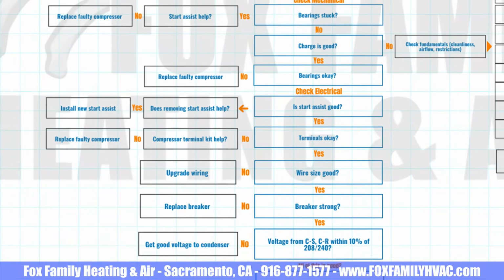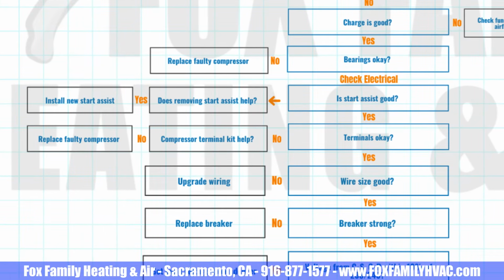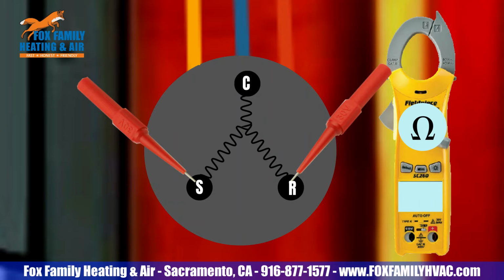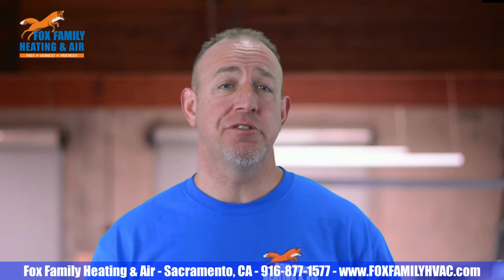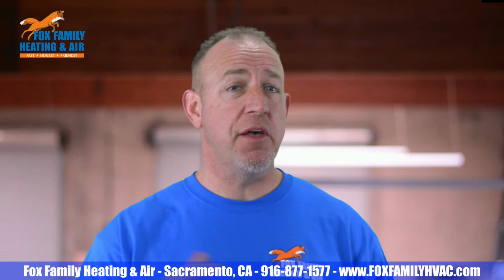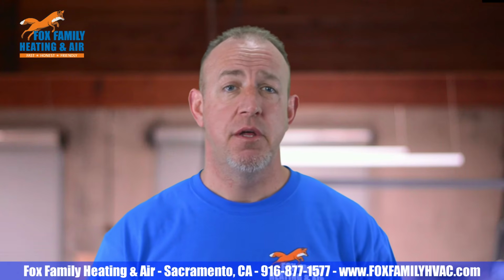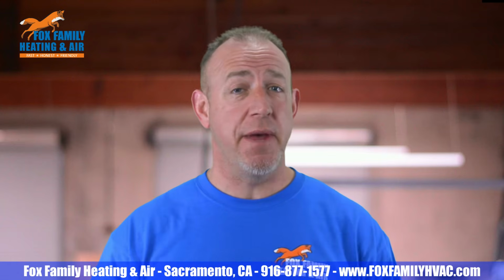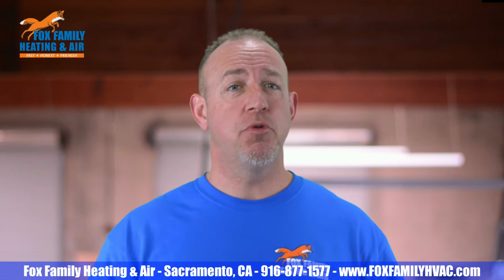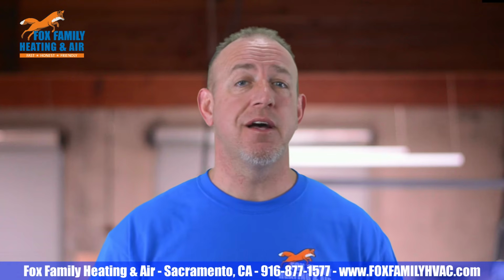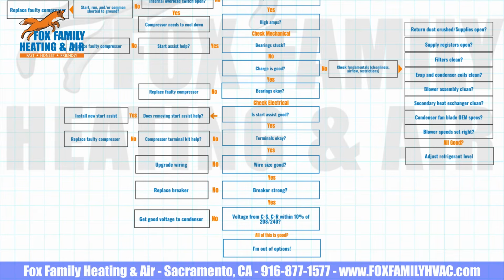Here's another thing to check on the electrical side, and you may have already noticed this when you were ohming out the windings. Check for loose common, start, or run terminals. Check for burnt wiring or any charring or black soot around the terminals. Most compressors have a rubber plug for the female end of the connection to the compressor, but there are some that just have plain old spade connectors. These poor terminal connections could be creating a line voltage problem at the compressor.